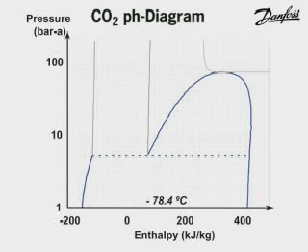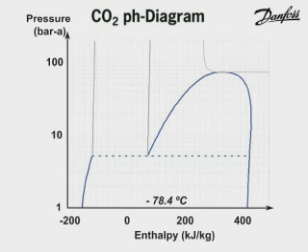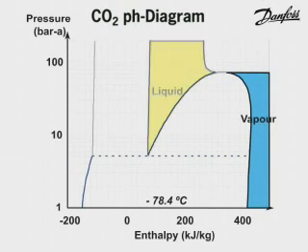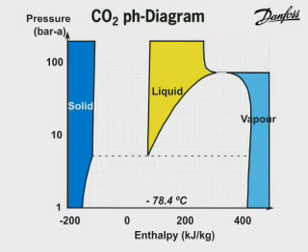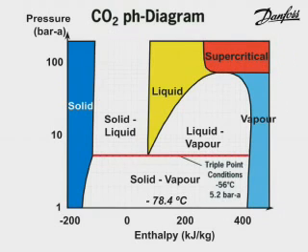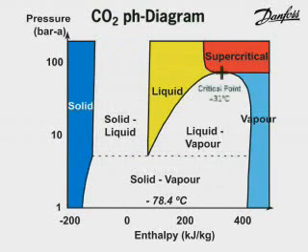For refrigeration purposes, the pressure-enthalpy diagram is commonly used. For CO2 applications, this diagram has to be extended so that the solid and supercritical phases are included. The coloured areas indicate the different phases of CO2, namely vapour, liquid, solid and supercritical. The triple point is here. The critical point is here.